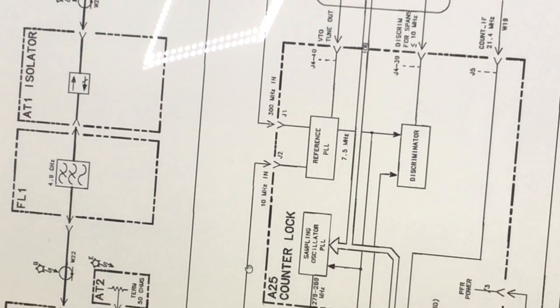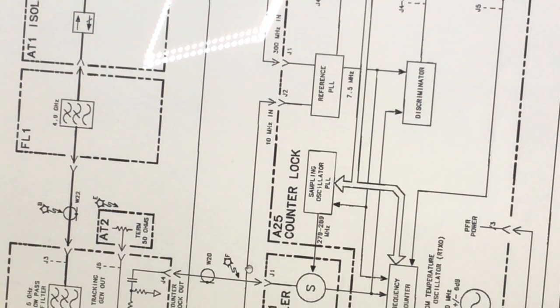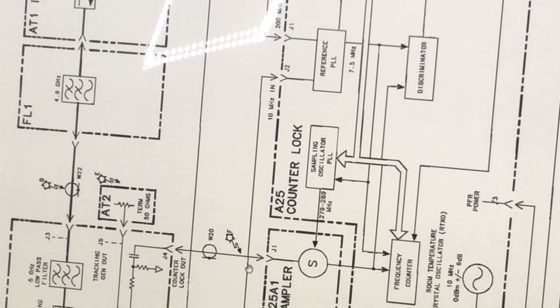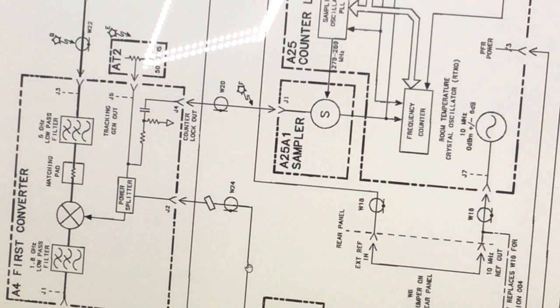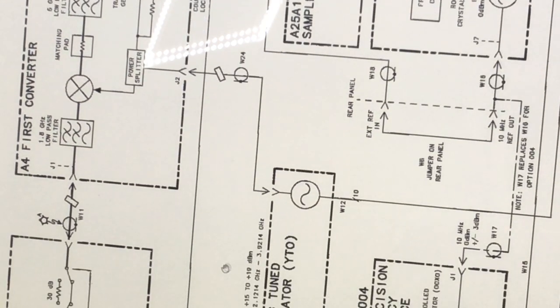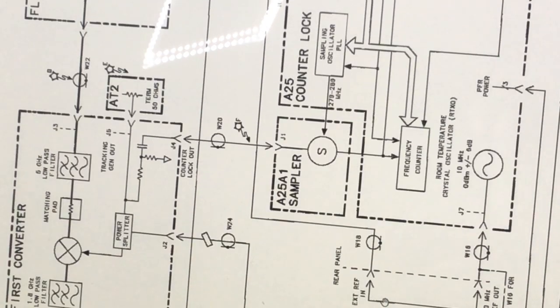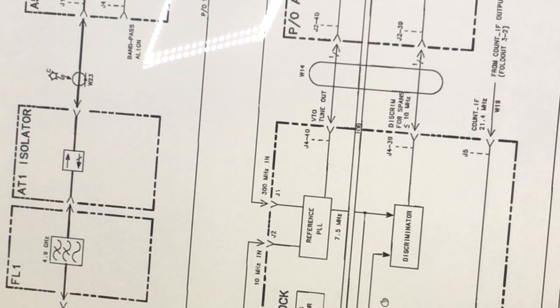We've got a 10 megahertz TCXO, temperature controlled crystal oscillator, input there as well, which is derived from this, which would be an option if that was a high stability one. But in this case it's just that little PCB with a can and a little trimmer capacitor in it that we were looking at earlier. So the 10 megahertz signal's there because we verified that it could be tuned and adjusted, and the DAC value changed its frequency as well as physically tuning the capacitor within the 10 megahertz oscillator.